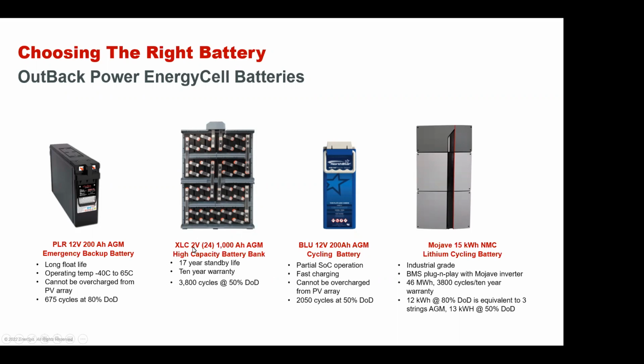Now we have our XLC high capacity battery. It's got a 17-year standby life, and a 10-year full replacement warranty as long as it's been monitored during that time. 3,800 cycles at 50% depth of discharge. That's like lithium ion cycling ability. So that's a really nice battery.